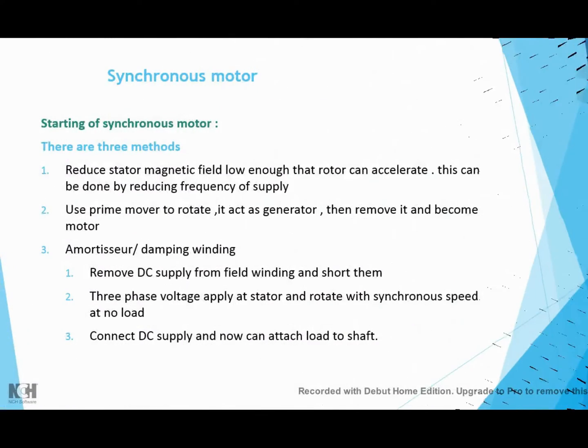There are three starting methods. First, reduce the stator magnetic field low enough that the rotor can accelerate — this can be done by reducing the frequency of the supply. Second, use a prime mover to rotate it, acting as a generator, then remove it so it becomes a motor. Third, use amortisseur damping winding.